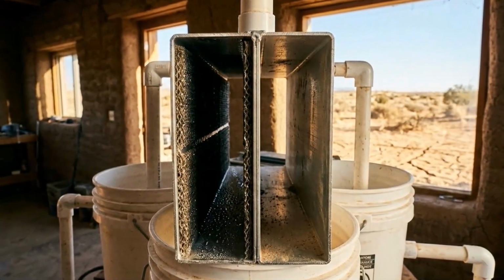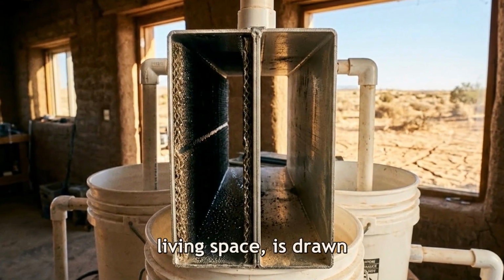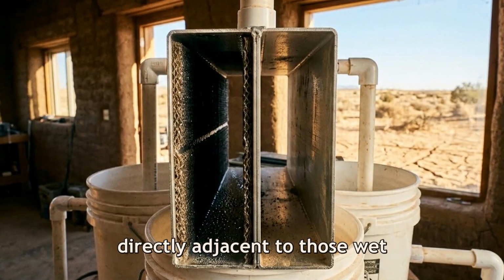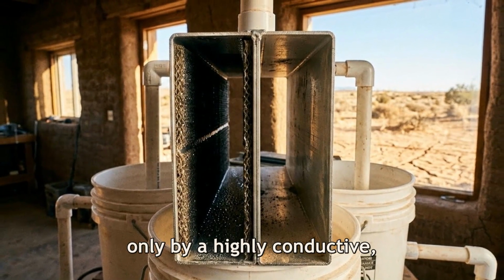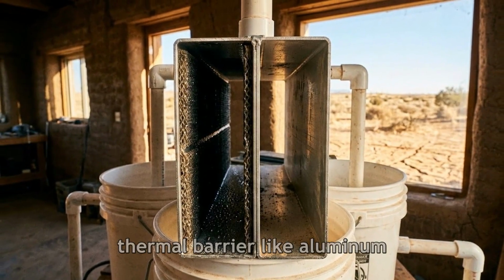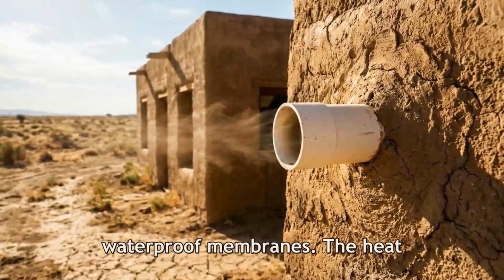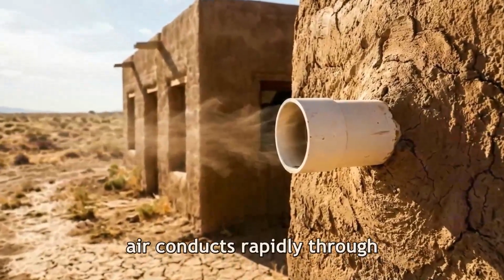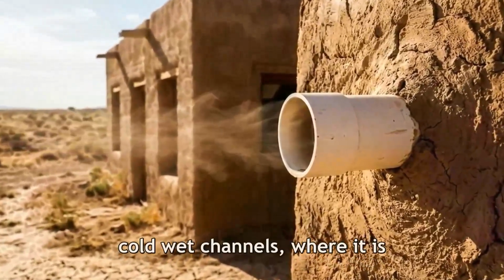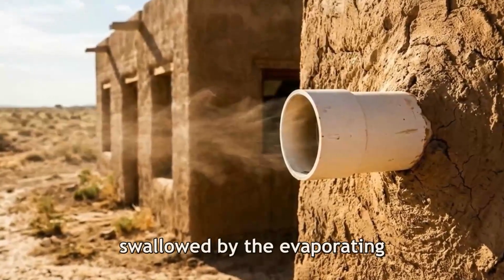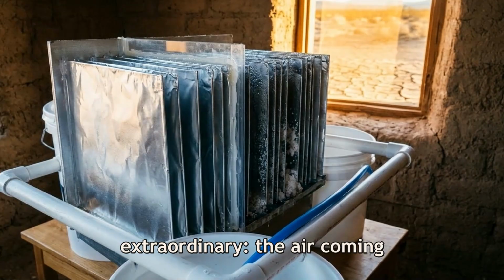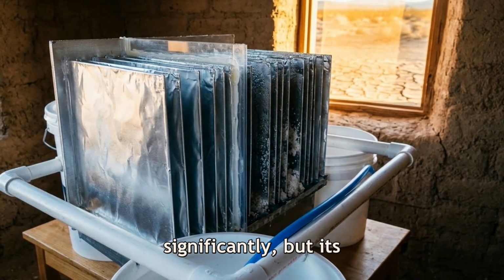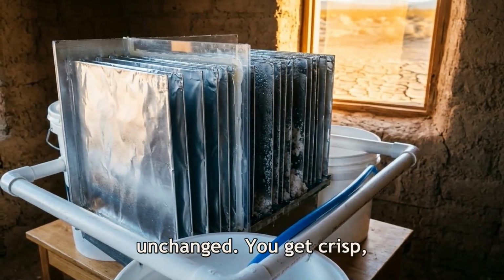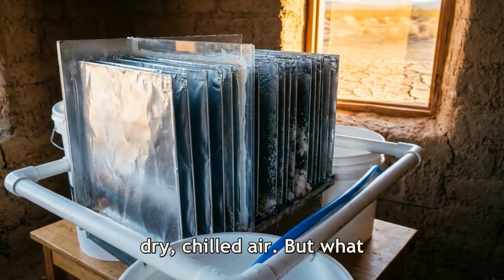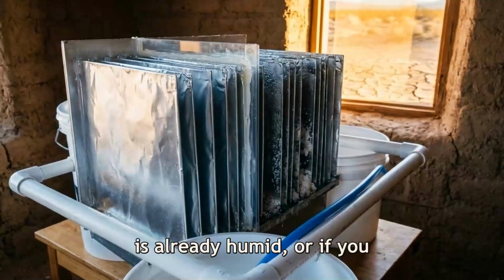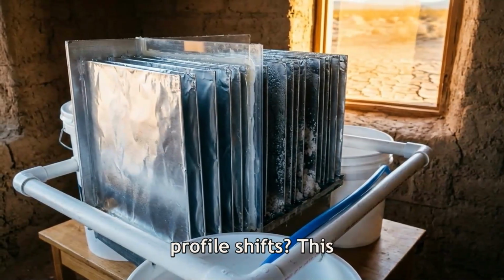Meanwhile, the product airstream, the fresh air meant for your living space, is drawn through a series of completely dry channels, running directly adjacent to those wet channels, separated only by a highly conductive, ultra-thin thermal barrier like aluminum or specially treated waterproof membranes. The heat from your dry product air conducts rapidly through the barrier into the freezing cold wet channels, where it is swallowed by the evaporating water. The result is extraordinary. The air coming into your house is cooled significantly, but its absolute humidity remains completely unchanged. You get crisp, dry, chilled air, but what happens if the outside air is already humid, or if you need continuous cooling at night when the temperature profile shifts?